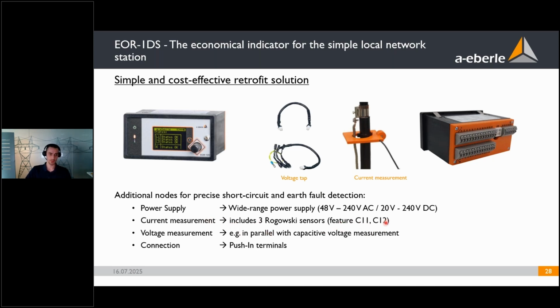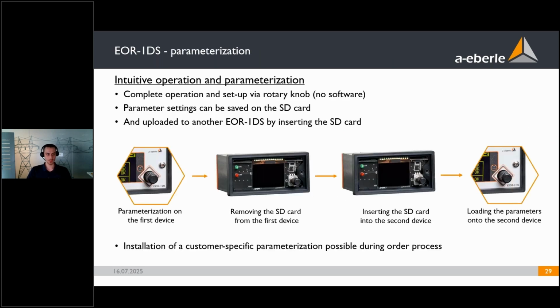You have the current measurement via Rogowski sensors and voltage measurement, for example, in parallel with the capacitive voltage measurement. And the connection would be done using these push-in terminals. They are also quite easy to handle. As it says in the name, you just push in the connector and then it's installed. The parameterization and firmware updates as well are also really easy and intuitive.